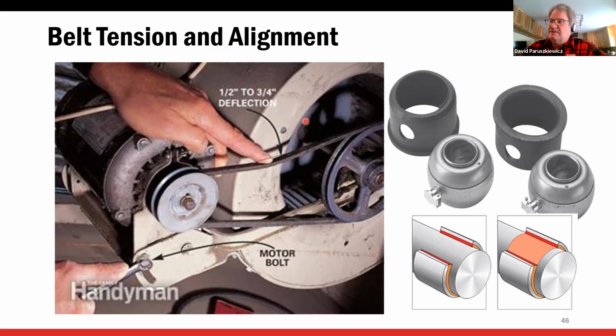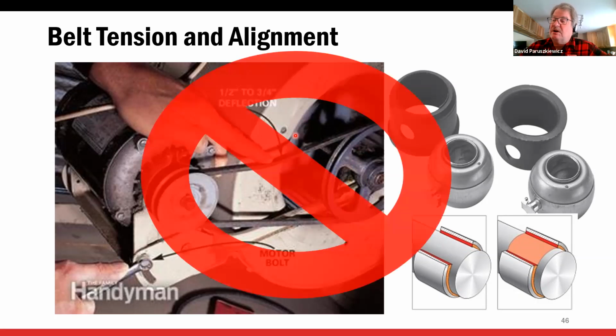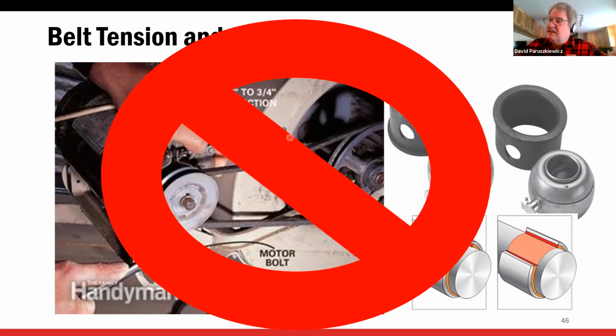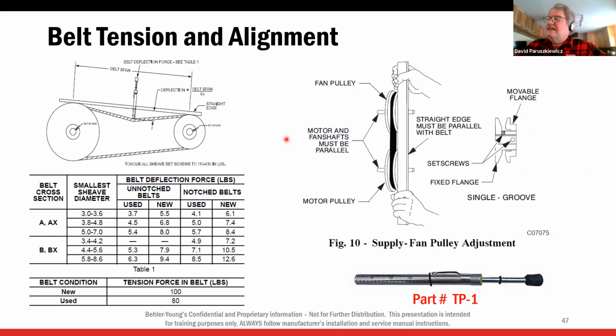This picture here that you're seeing is wrong. That's way too loose. Like I said, out of those hundreds of contractors at the expo, so mostly owners and bosses, only 5 of them got the tension correct. So don't cause yourself problems by not tensioning these belts properly. There is a special tool for tensioning belts, this little picture down here on the right. I have not seen a digital version. It's pretty simple and pretty inexpensive, but we need to properly tension these belts to get the proper airflow. Also, the belts will last a lot longer if they're tight enough.